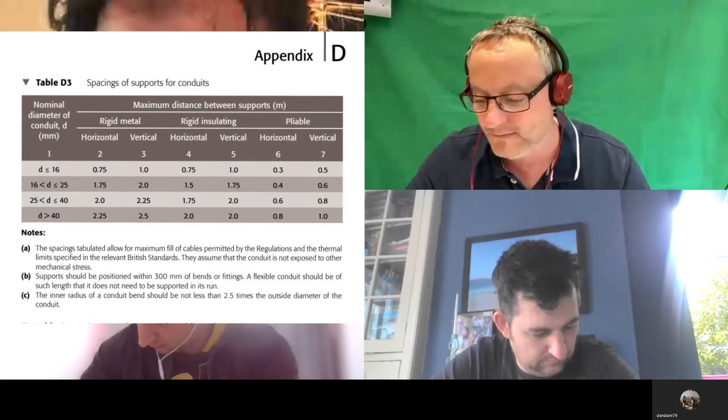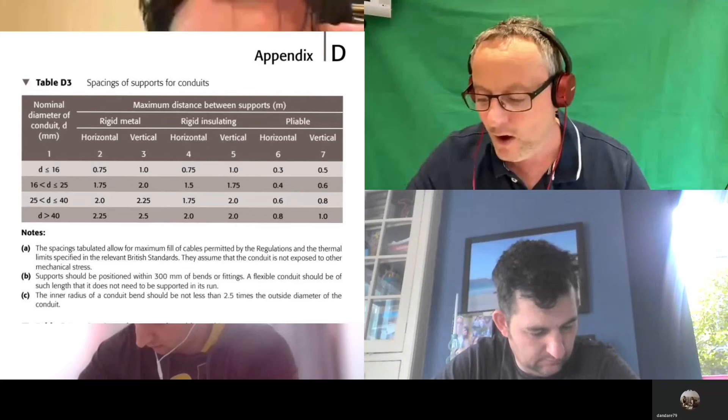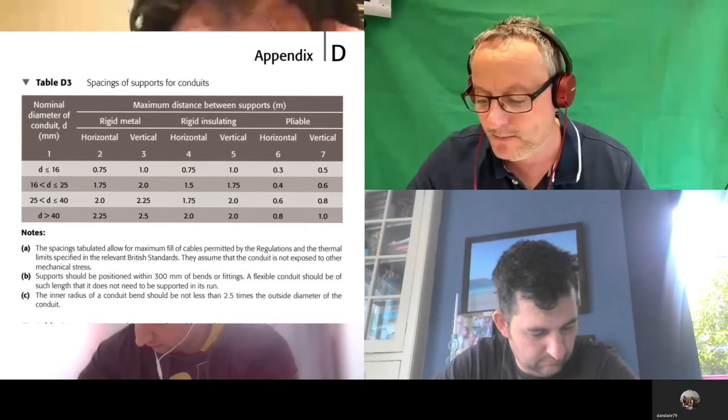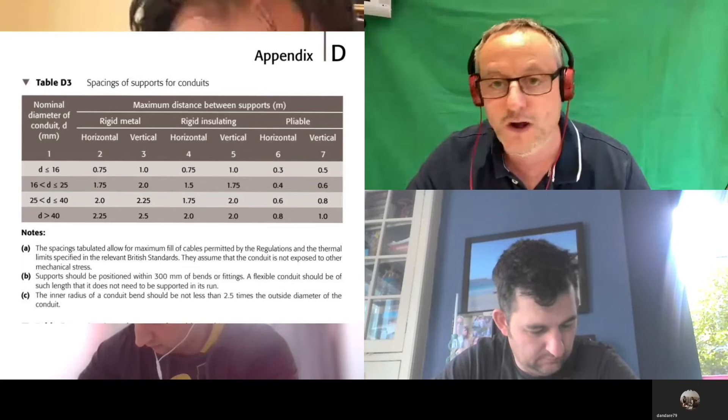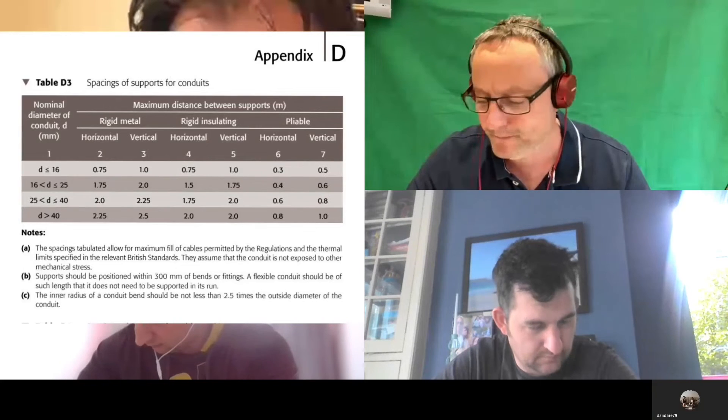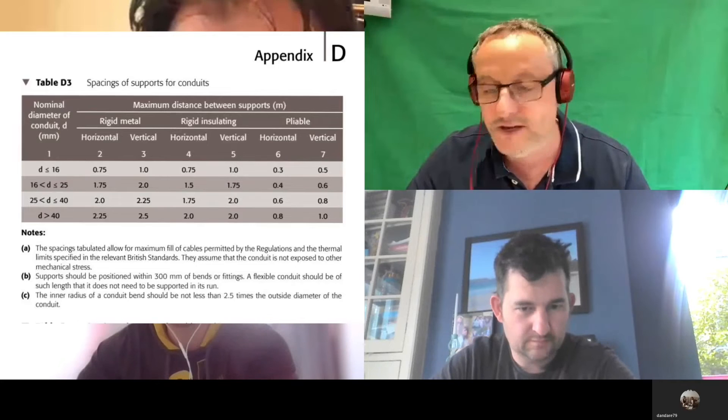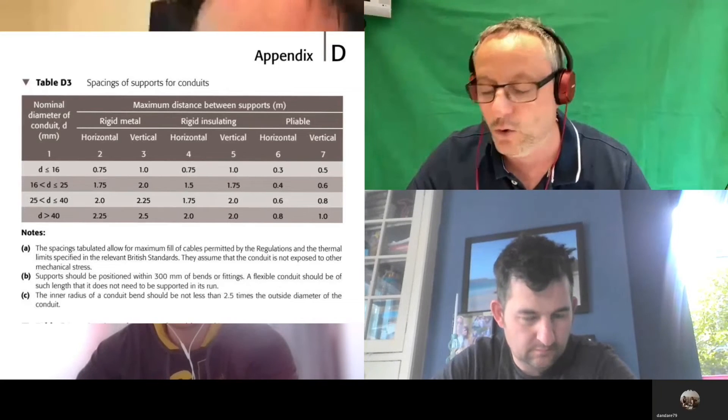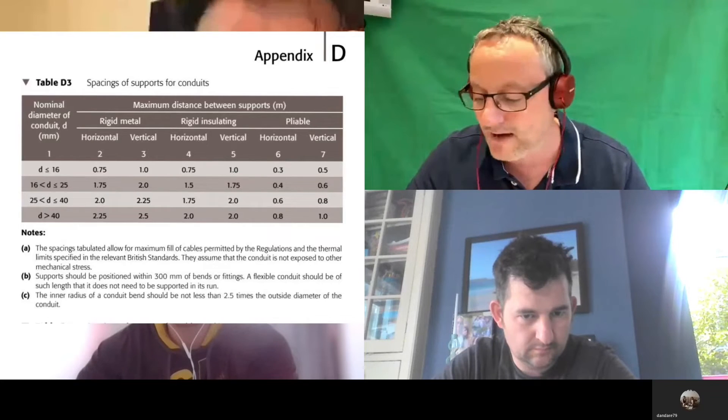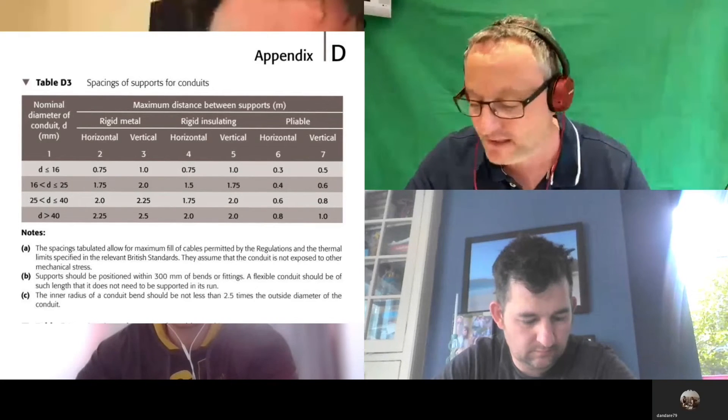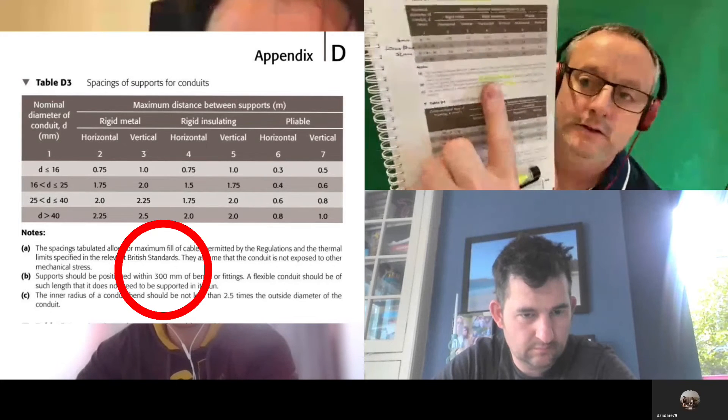We're going to use that table in a second and you're going to fill that in your notes. Let's look at the notes below that table D3. There's some really important bits in there for us. If you look at Note B, I've highlighted the maximum distance away from a bend or fitting that I can have my support: 300mm. So when you put a bend in or socket box or switch, you should have a saddle securely fixing it within 300mm.